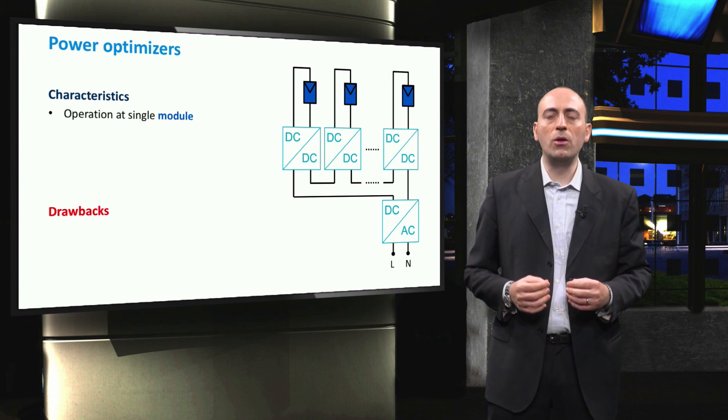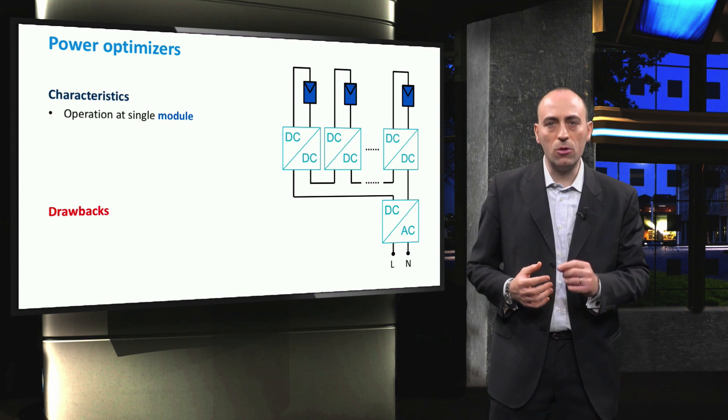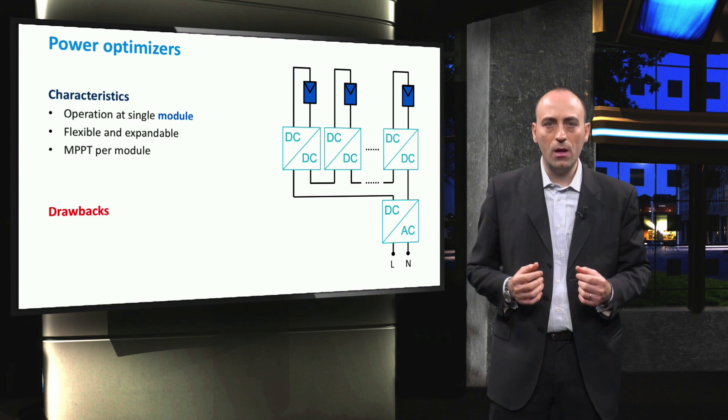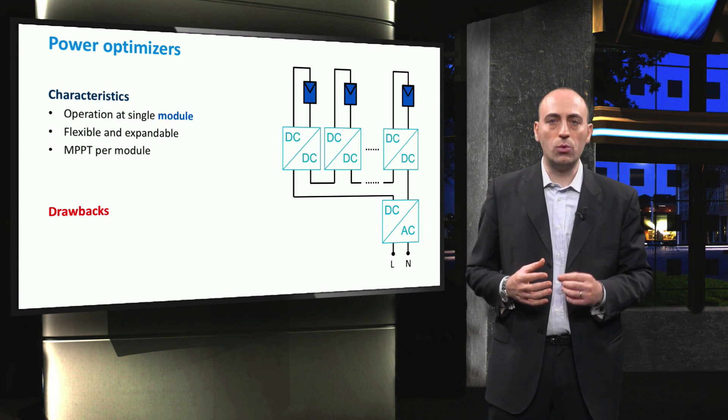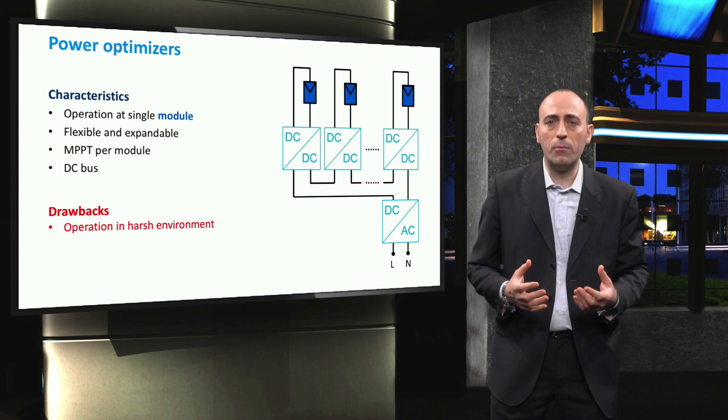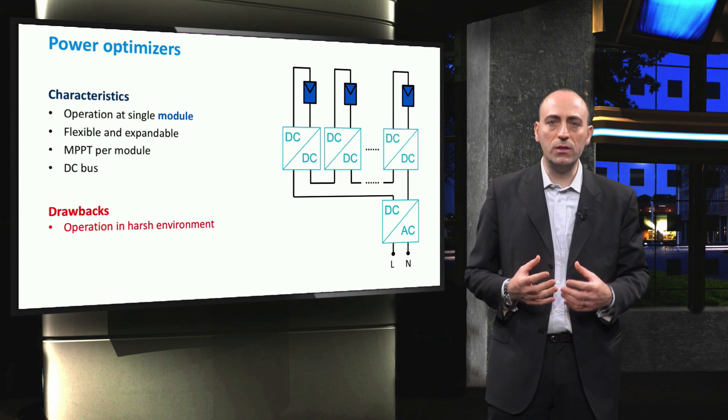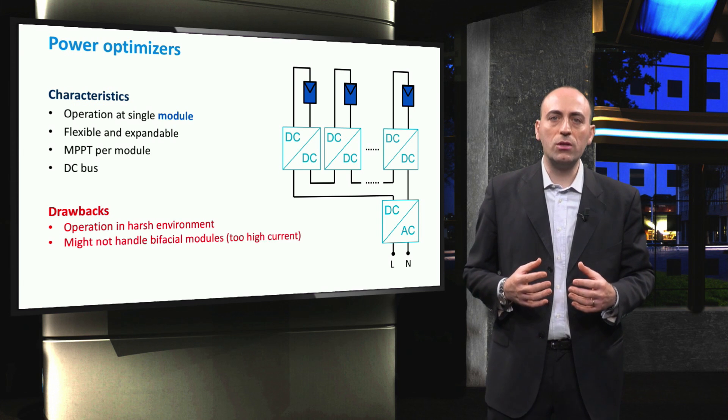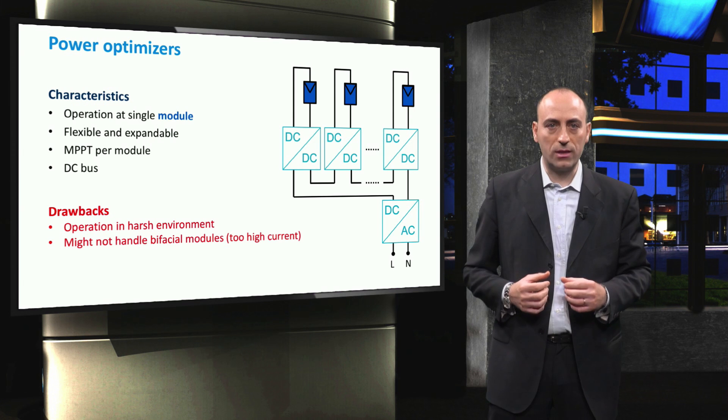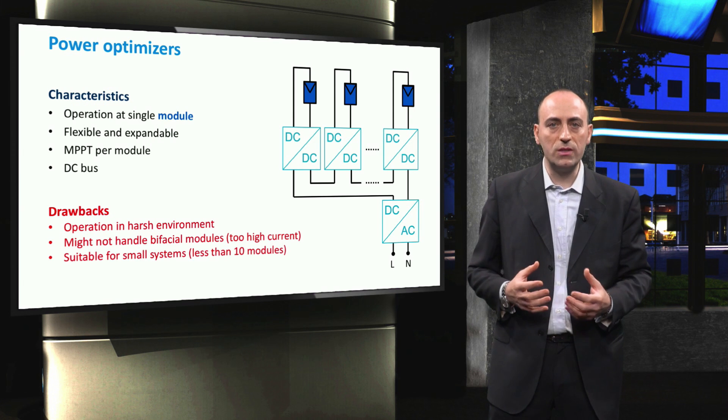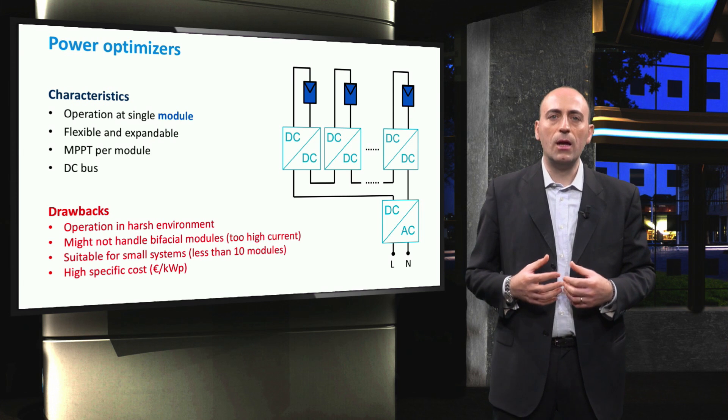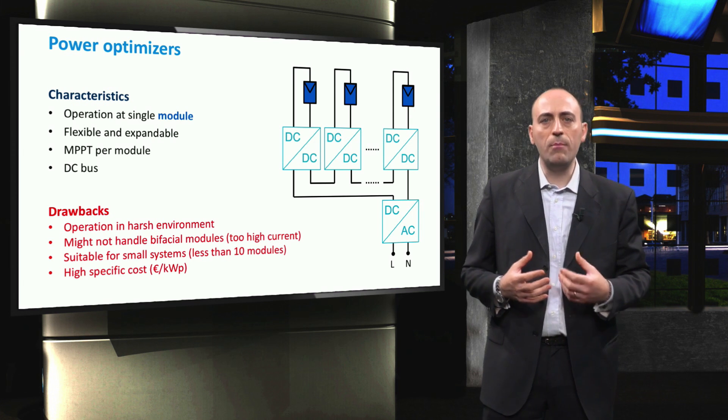Similarly to the previous case, the topology based on power optimizers relies on operations at single module level. It is especially flexible for roofs in urban environment and expandable to a certain extent. Power output is optimized by offering MPPT at module level, and installation is simplified because of the DC bus topology. Passing to the drawbacks, also this topology needs a sturdy embodiment for the power optimizers to be mounted and operated safely at the back of each module. In addition, newer bifacial modules, which promise higher current levels, may not be supported by current technology. This topology is suitable for small systems up to about 10 modules. For larger systems, limitations on voltage and specific costs become too stringent for this topology to perform well and be economically viable.